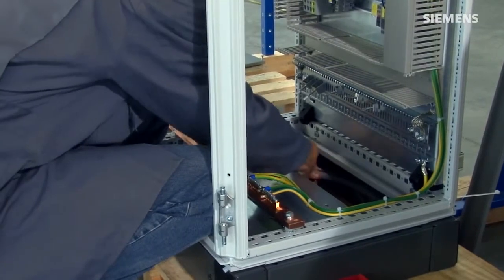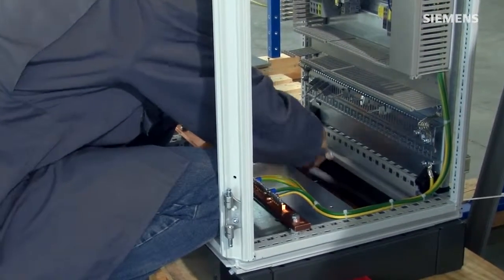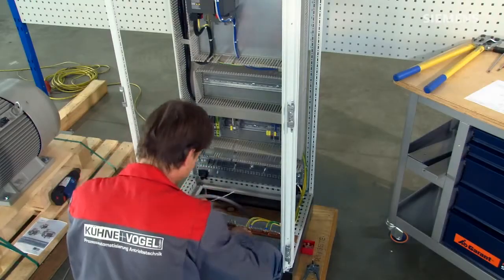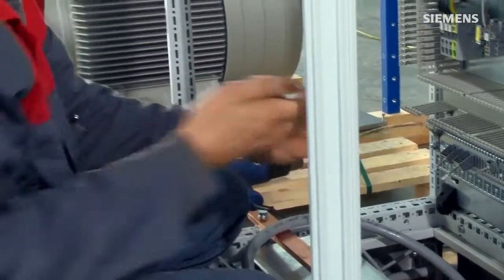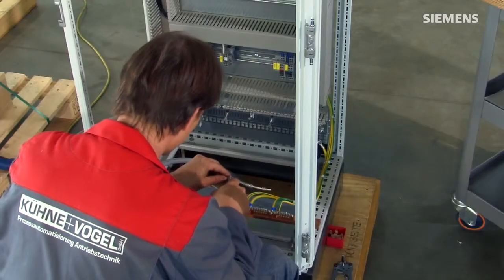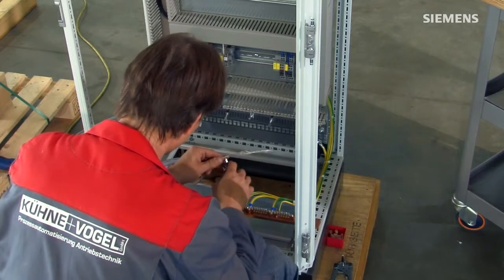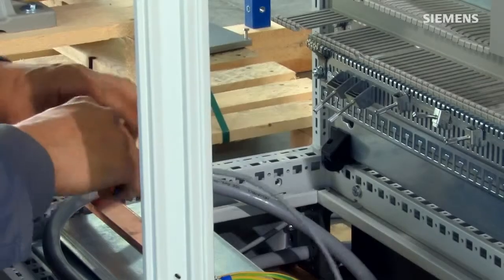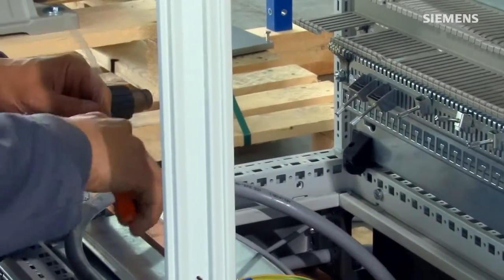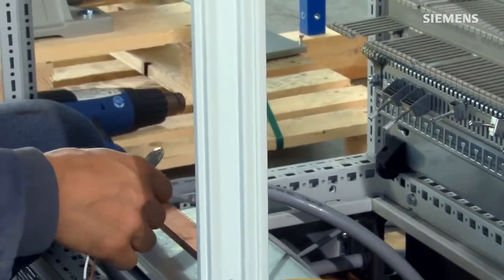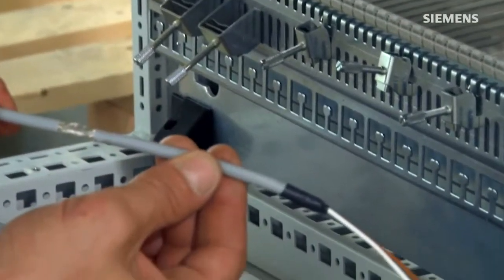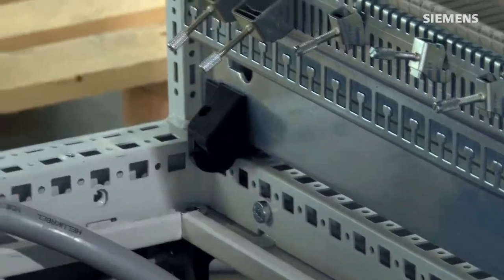First I'll pull the cable out of the socket area. Then I'll strip the PTC cable and cut away the shield, leaving around 1 cm in place. Crimp the excess shield over the outer jacket. Then seal it with a shrink-on tube or a rubber grommet.